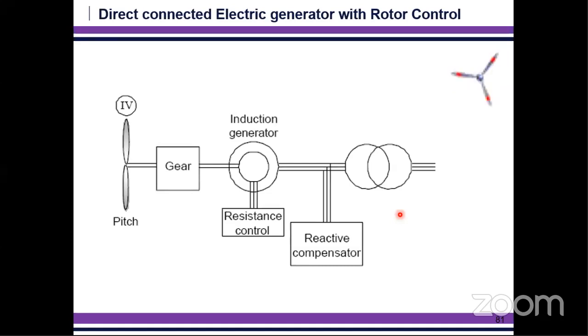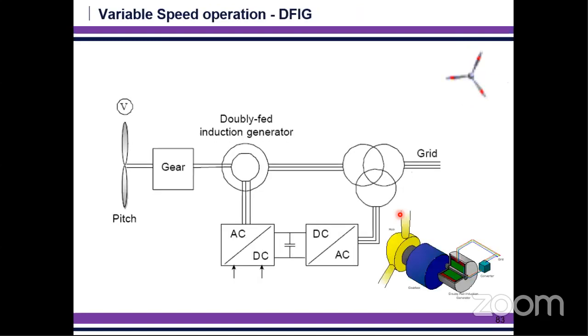The second type is where you can use slip ring induction machines as a generator, and here you can do resistance control in addition to the existing configuration. The third one uses a partial size converter. You can see the picture: this is the gearbox, and you can see the stator. The converter size is very small, because the converter is connected to the rotor side. Normally, you know very well, the rotor parameters are much smaller than the stator parameters. So there are big savings in size as well as cost, and it does the same job as the other big size converters.